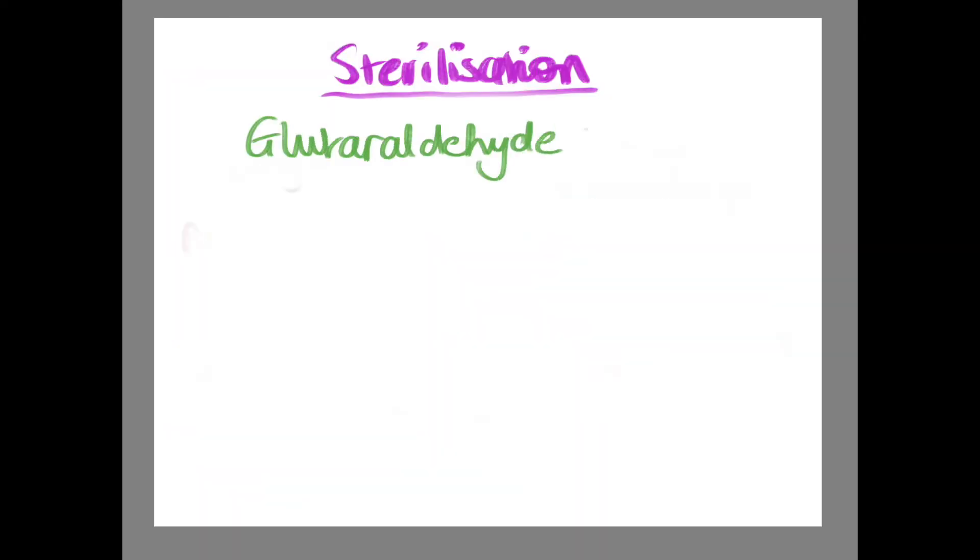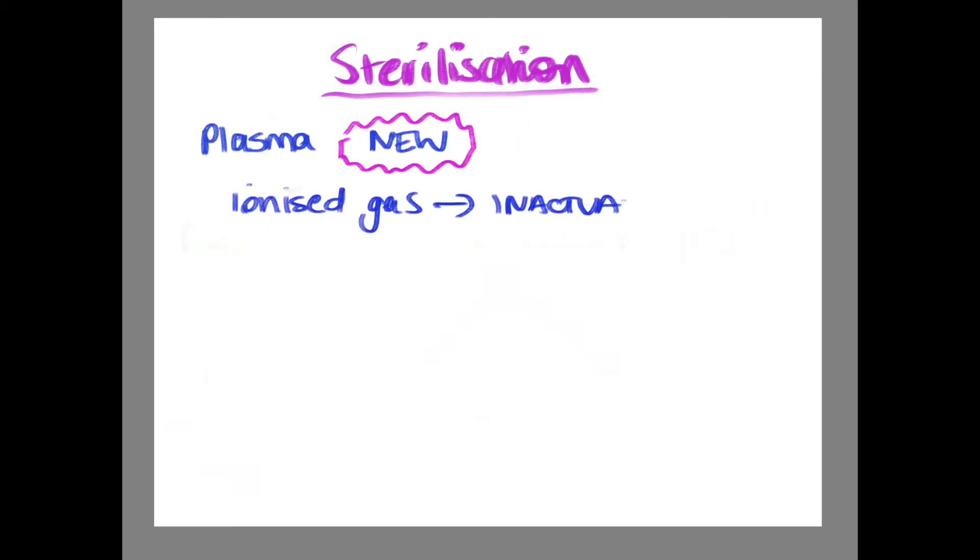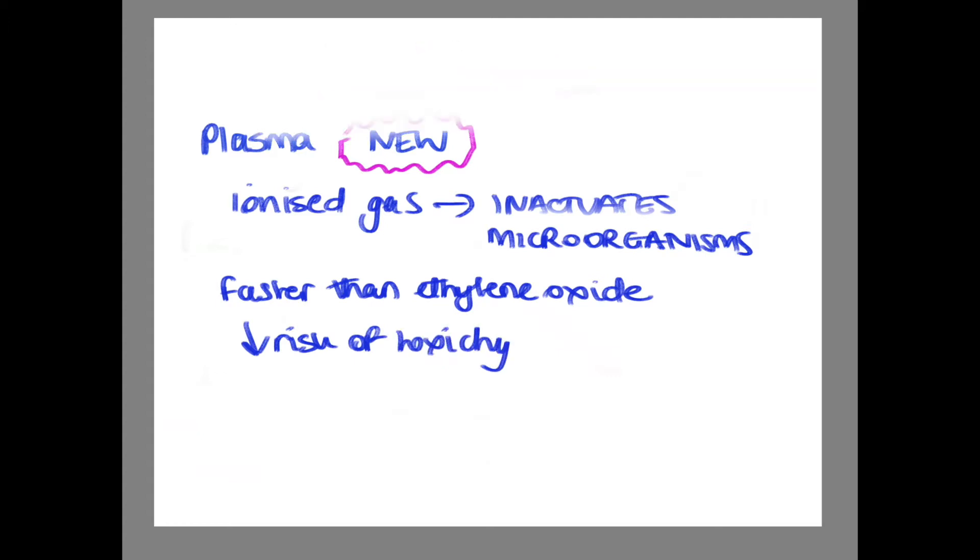Glutaraldehyde 2%: This method tends to be used for optical equipment such as scopes. If used for less than around 10 hours, then sterilization is less likely to occur and equipment may only be disinfected. Plasma is a newer technique. This is an ionized gas containing free radicals which inactivate microorganisms. It is a shorter sterilization time compared to ethylene oxide with a lower risk of human toxicity.